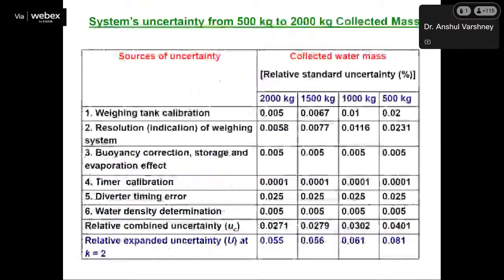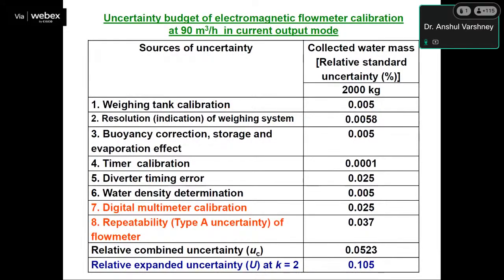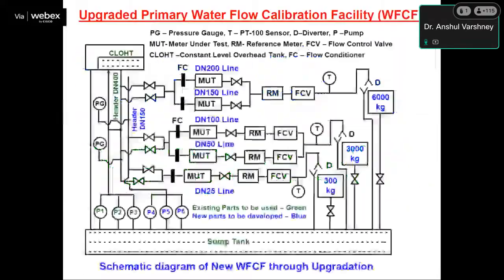This is the diverter error calculation, and this is our upgraded primary flow calibration facility. Right now we are providing calibration in this facility. Basically, we have 6 pumps: 3 pumps of 50 HP and 3 pumps of 3 HP, 5 HP and 10 HP. There is an underground water tank.